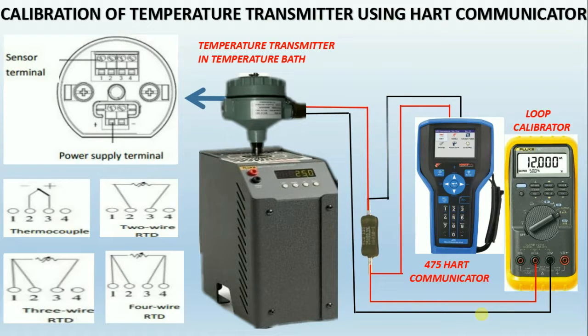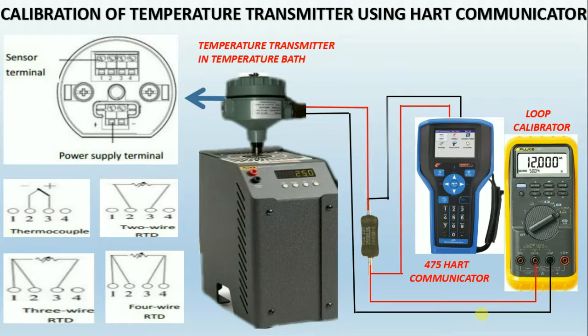After this, set the full range of the transmitter in the temperature bath and check the corresponding 20 milliamps. If it is not showing the corresponding milliamps, then adjust 20 milliamps by doing the upper sensor trim using HART.